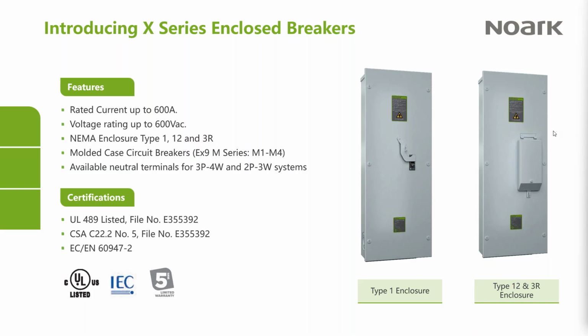Perfect, thank you. And just following up on the points you made about the environmental conditions they can handle: how are they designed to handle those, and what standards are they meeting to withstand those conditions? Right. So the enclosure ratings are driven by the UL and CSA standards. Under UL, it's UL 50, and they provide very detailed descriptions of the construction and of the testing requirements. And then one of those organizations must witness the testing. This brings us to Type 1, Type 3R, and Type 12, which is what our products here are rated for.